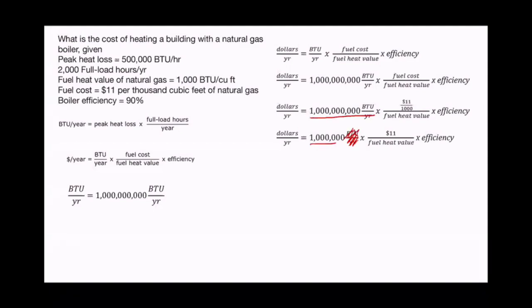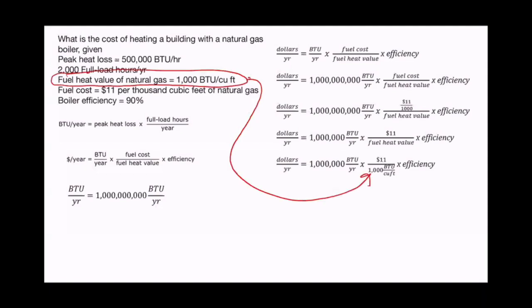Our dollars per year is 1 million times 11, divided by the fuel heat value times the efficiency. We need the fuel heat value of natural gas, which is 1,000 BTUs per cubic foot - meaning for every cubic foot of natural gas, we theoretically get 1,000 BTUs out of it.